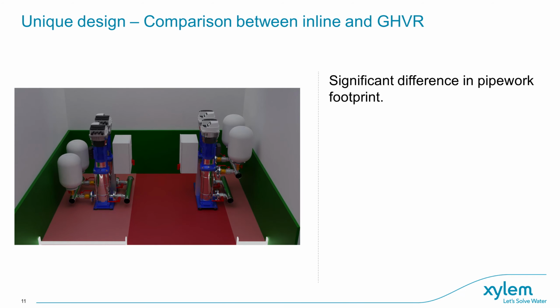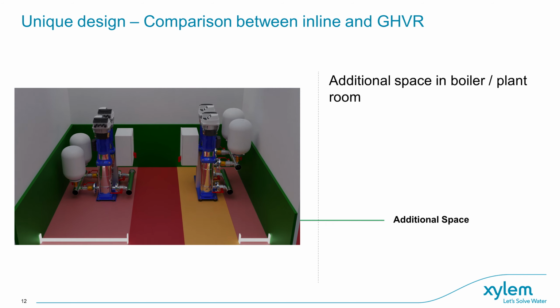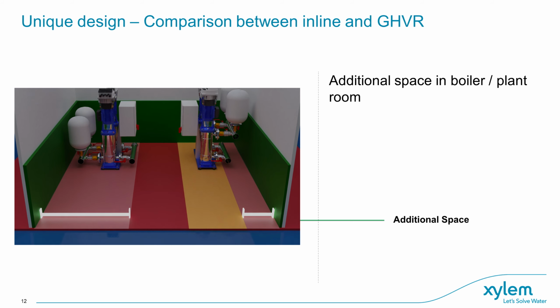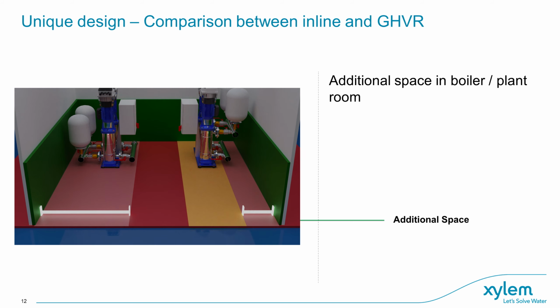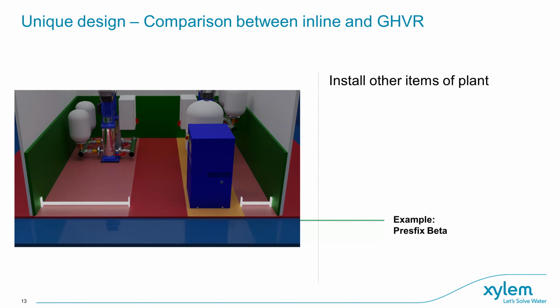So in a typical real-world application, compared to an inline booster set, the footprint of the pipework is significantly reduced. You can see this with the shaded area shown in the graphic. This ultimately gives the installer more floor space within the plant room. The yellow area shows the extra floor space now available. The real-world benefit to the installer is that they can now fit other equipment in the newly available space.